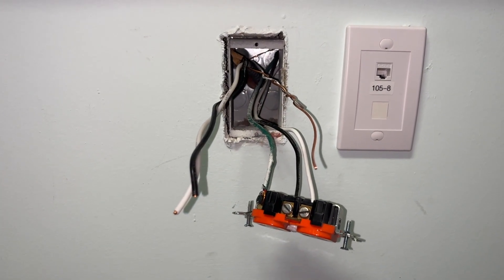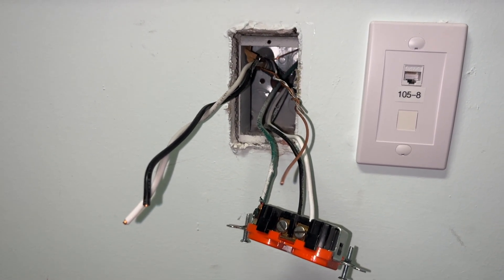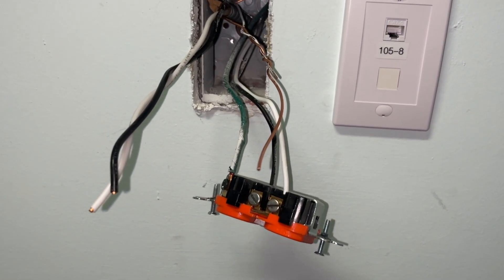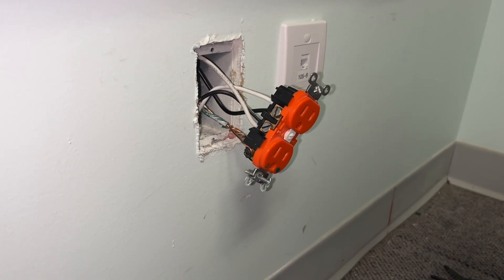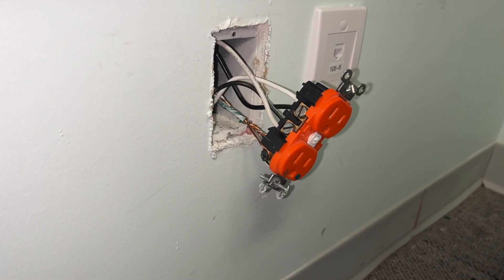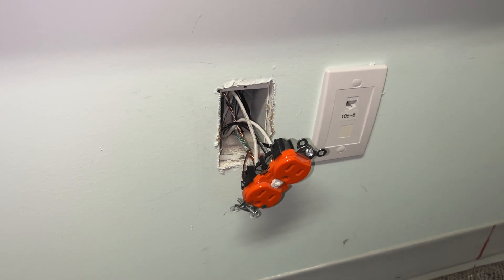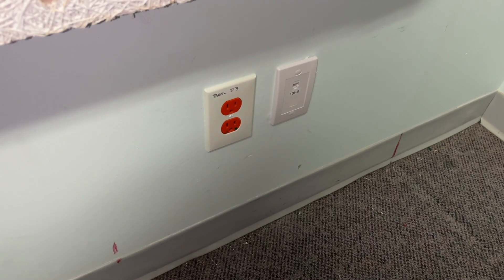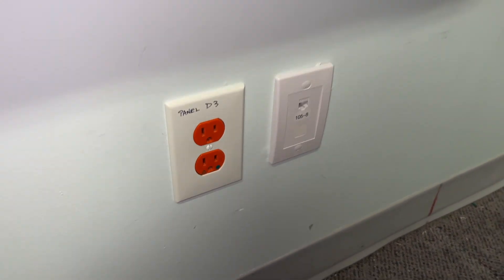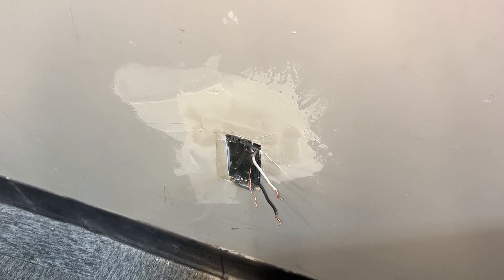As far as interconnecting this outlet on this side of the wall with the one on the other side, this will be super easy. Even though this is an older outlet, you can see the wire connections on the side of the receptacle — they are actual lugs, and they are bridged. That makes it real easy to just connect my wires to the back of the receptacle itself. I use the receptacle as my connection and run the wire straight through to the other side. You couldn't do this with a regular residential type receptacle — they're just too lightweight, not built this way. But with this one, we can do it safely. This side of the wall is done. Tomorrow, on the other side of the wall, when my mud is dry, I will sand and touch up paint this, and install the other receptacle.